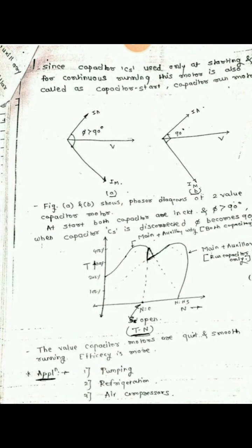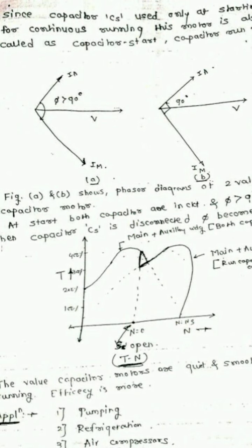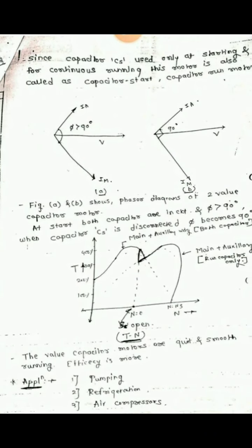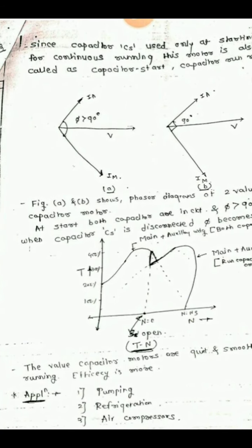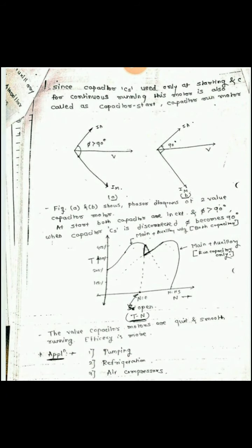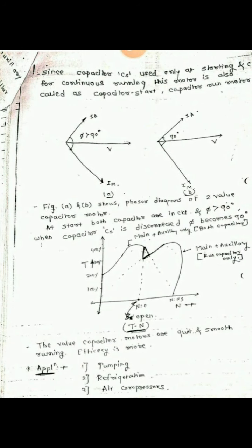The torque-speed characteristics of the capacitor start capacitor run motor show torque on the Y-axis and speed on the X-axis. At starting, both the main and auxiliary windings with both capacitors are in the circuit. After the centrifugal switch S opens, only the run capacitor remains in the circuit with the main and auxiliary windings. This motor uses the capacitor for both starting and running conditions, making it quiet and smooth running.